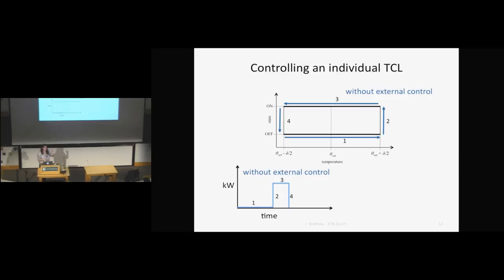The cool thing about these loads is as long as I keep them within this deadband, the customer doesn't care - the person who owns the device only cares as long as the temperature is between these two bounds. So to extract flexibility from these systems, I can imagine a system where, again, I'm drifting this way, but then I get a big gust of wind in my system, so I flip it on. Then it starts powering down this way, and then the wind goes away, so I flip it off. So I have flexibility in the system because I can change when I go up and down.